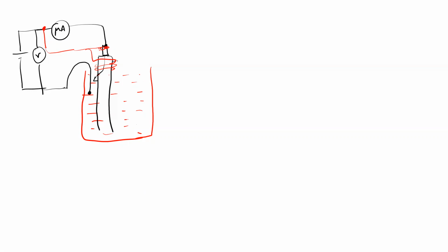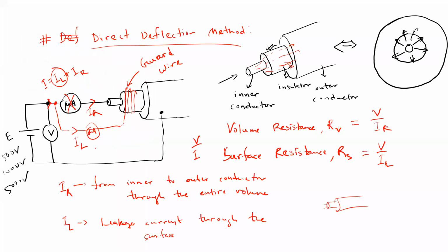Yes, there will be some problem, as I mentioned while discussing this circuit, because the magnitude of the current is very low, and that will be a factor. If you place the voltmeter there, since the insulating material provides very high resistance, the voltmeter will actually act as a load, and most of the current passing through the ammeter will be the current flowing through the voltmeter. So it will not solely measure the current flowing through the insulating material, but will measure the current as a summation of both of these currents.